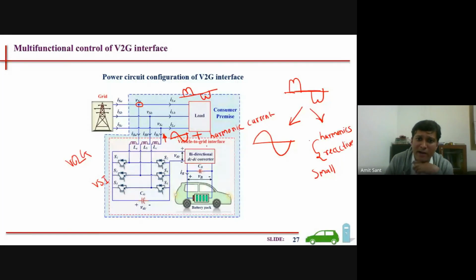So what will be the impact? Now the harmonic current is coming from this battery to the load. So the load needs harmonic current - it doesn't matter if it takes it from the battery or grid. So the load will say, okay, I have got harmonic current from the battery, I don't need it from the grid. So the grid current will be purely a sine wave.